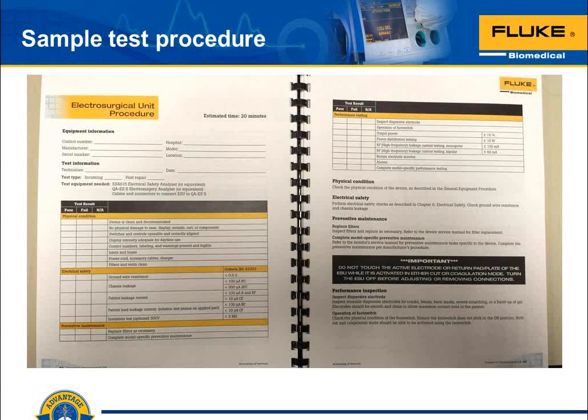Then we're going to do high frequency leakage tests and return electrode monitor circuit tests, and that includes those circuit alarms, and any other model-specific performance tests that may need to be done. So if you have a question in your mind about the difference between high-frequency leakage and the testing limits versus regular electrical safety, electrical leakage, and those testing limits, we encourage you to dig a little deeper, and there's information online available about that. We don't want to go into that topic too deeply in this particular webinar.